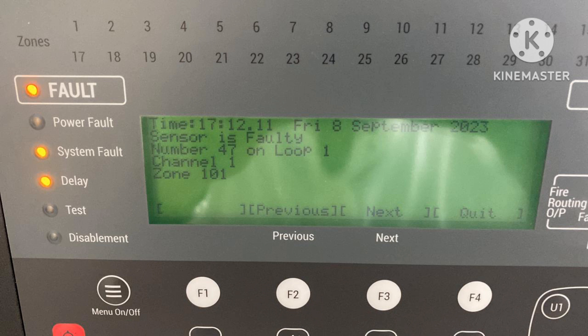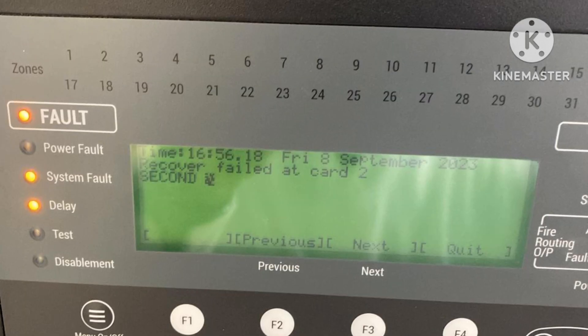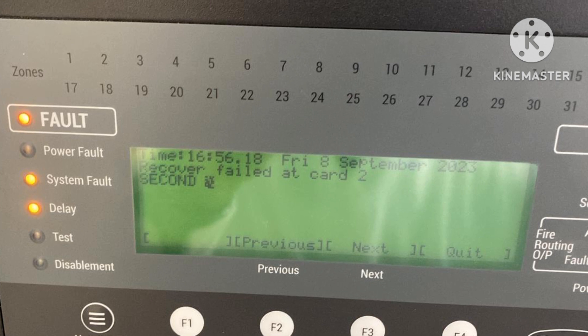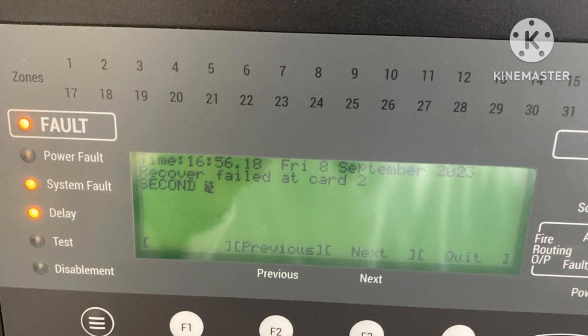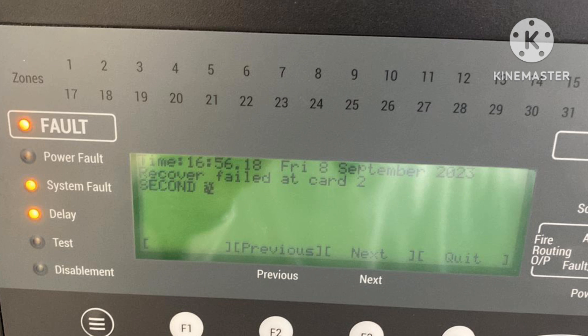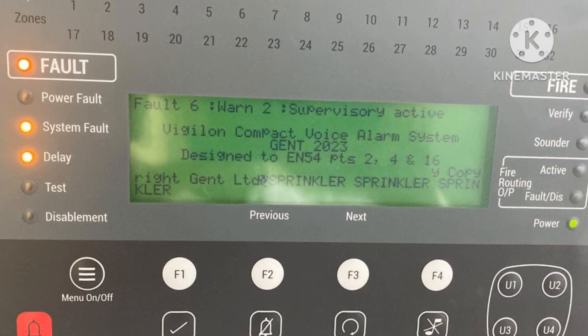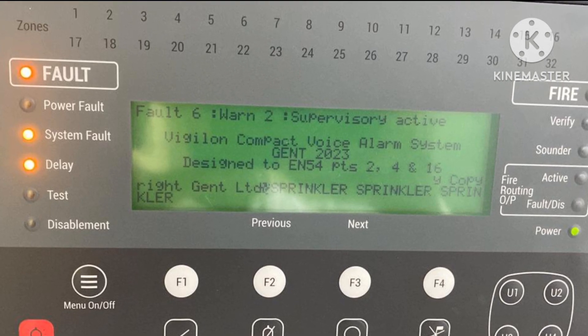System fault and delay — there is a 'recover failed at card 2' fault, which means the panel is not reading the previous data. Something has changed, so just back up the loop card. This fault occurs if you change or add something in the loop cable or devices. The panel reads devices every time, so if something is changed, the NVM data does not match. You need to back up the device in the loop card.